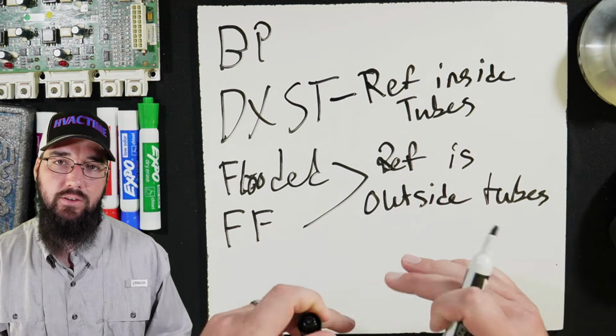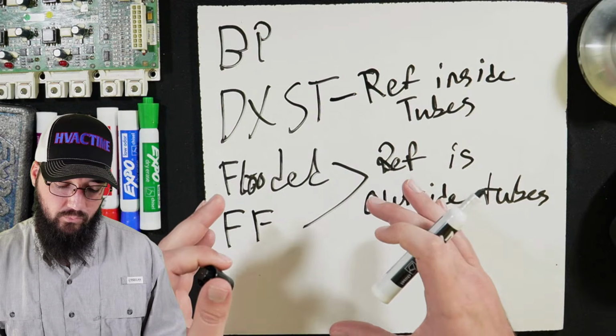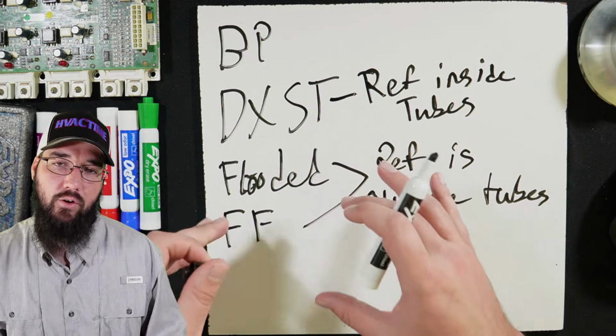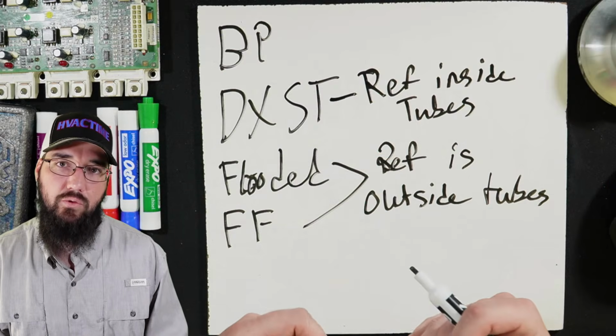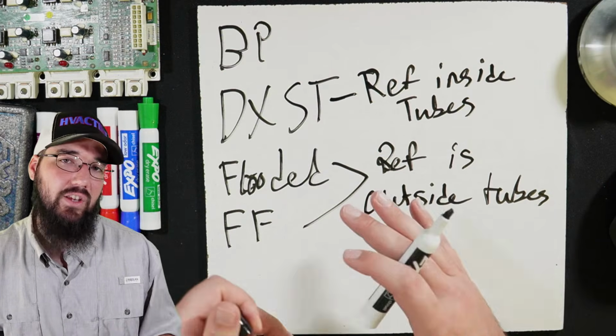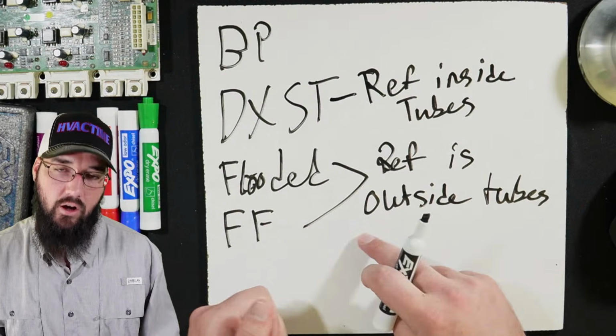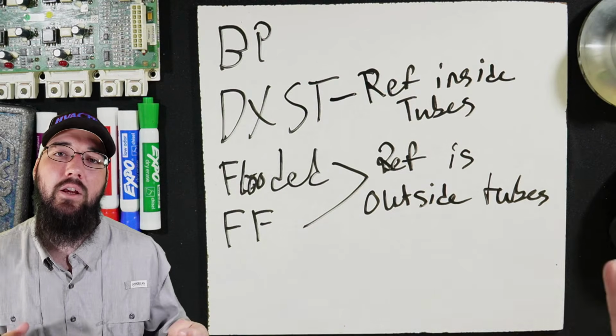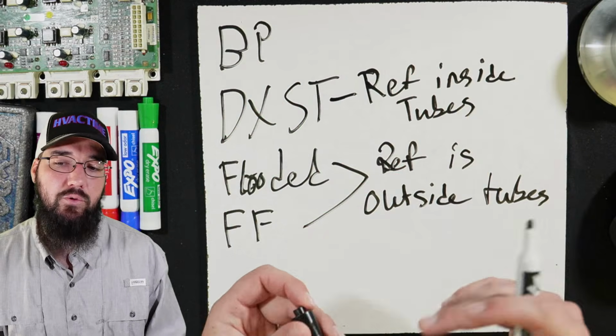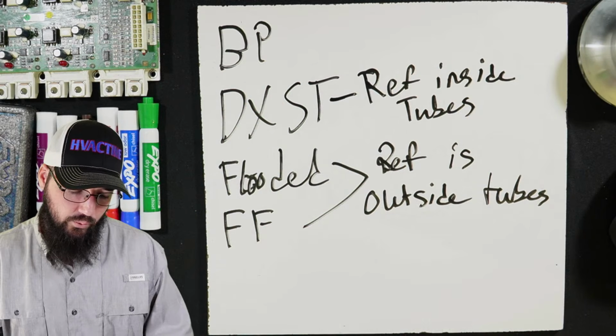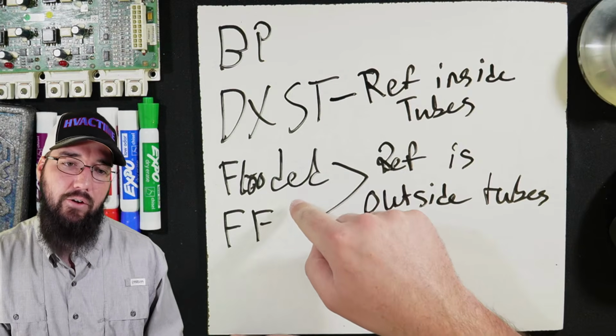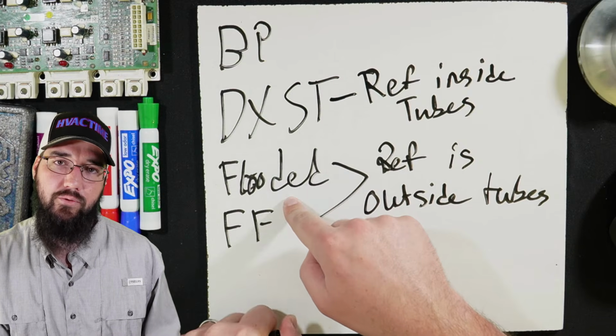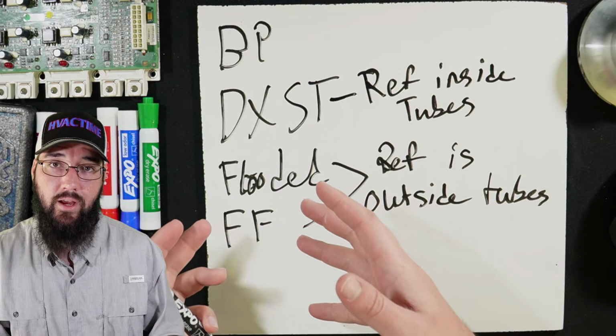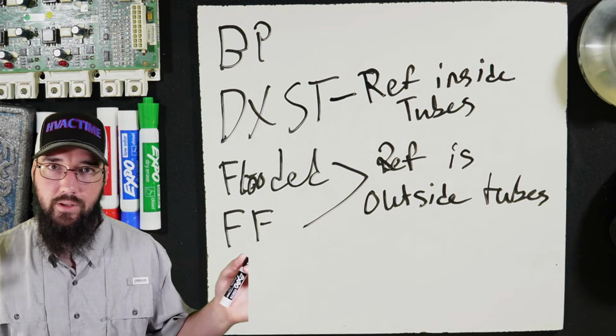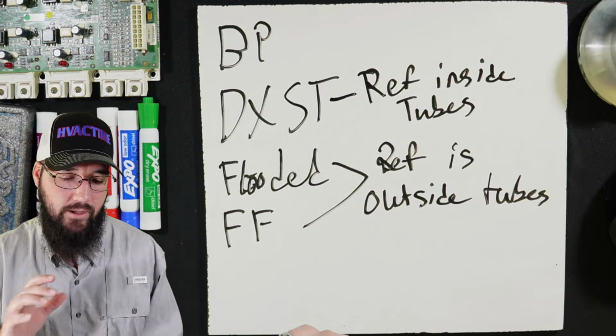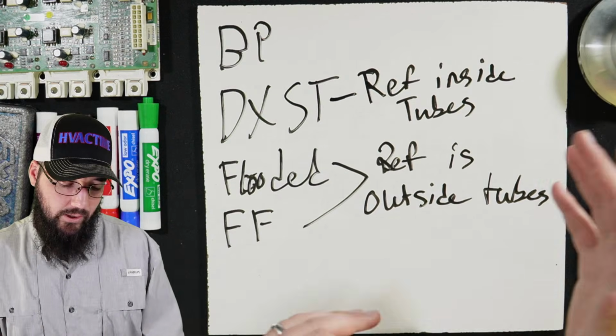Now, there are some machines out there that have the ability to do a pump down on these two styles. Like, you can do that, but that's the exception. Most don't. And when they shut off, they automatically let that refrigerant move into the evaporator, or at least the vast majority of it. So what's great about these is if we have access to that liquid refrigerant that's collected in these evaporators, with the exception of YVAA, as an example. Okay, we can get into those details separately.